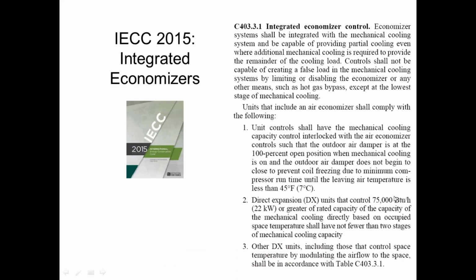All right, so I also have to do an economizer that's integrated. An integrated economizer is required by code. What an integrated economizer means is that my economizer damper has to work simultaneously and in conjunction with the compression when needed. It does require me to use the economizer first, so I cannot turn the compressor on until I've opened my economizer 100%. Then I can engage compression if needed.